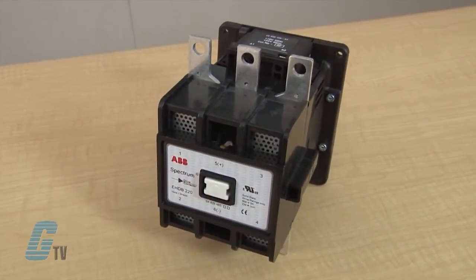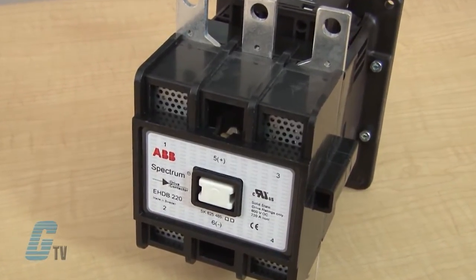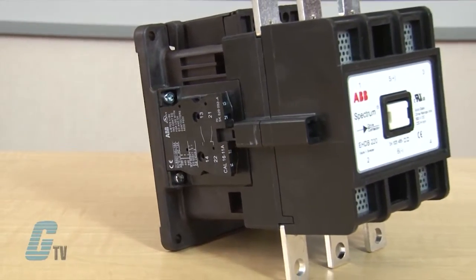The EHDB contactors are available from a range of 220 to 960 amps. They have mechanically interlocked contactors available for reversing applications. The double break contact design has a magnetic arc chamber that extinguishes arc in a short time and has a high temperature encapsulated coil.